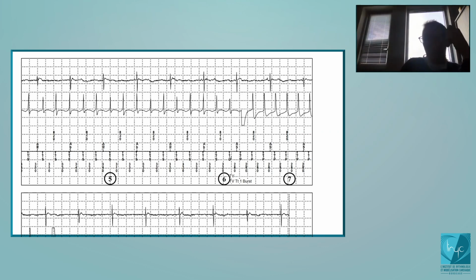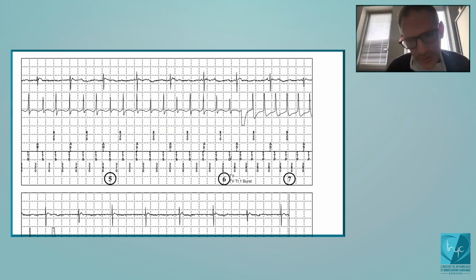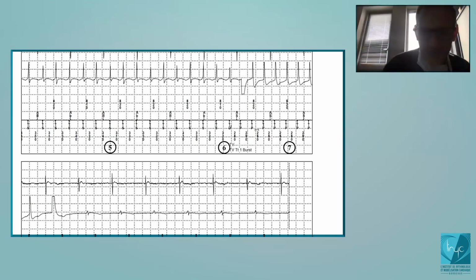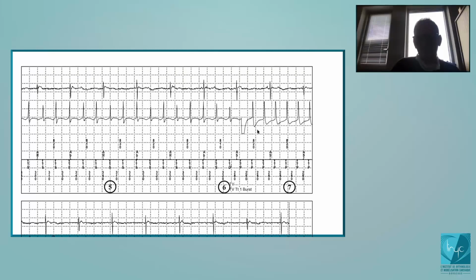And that's why, if you program high rates for your detection zone, like it is advised now, for example, up to a limit of 190 beats per minute, you cannot use the VT counter, because the VT counter can be used only for a tachycardia slower than 200 beats per minute. Okay, that's quite a rule that we try to apply every day when we program this kind of devices. Are there any questions here?